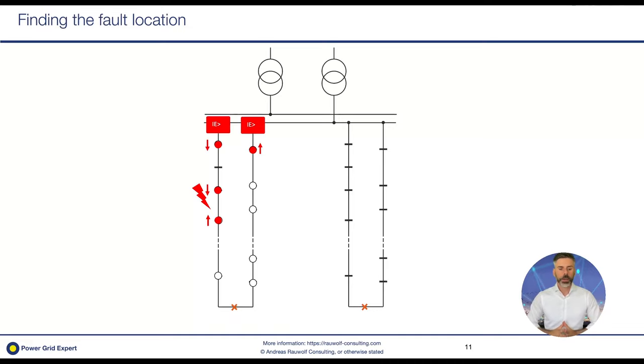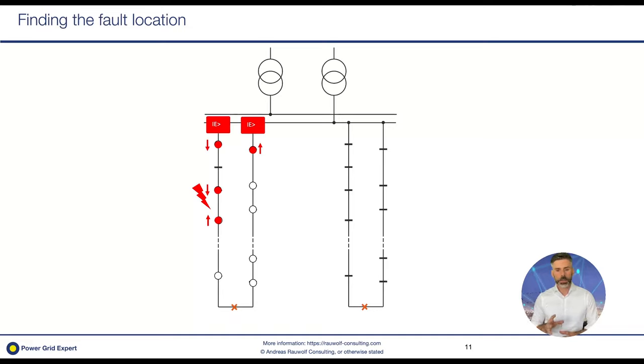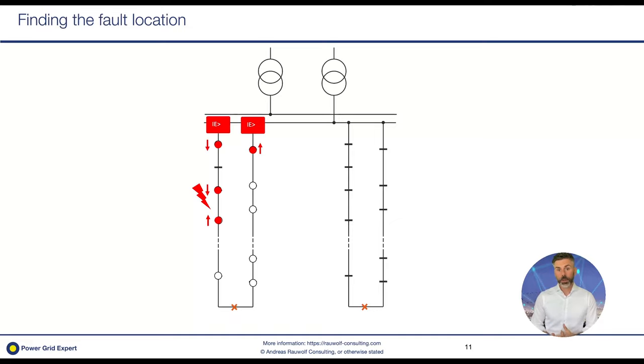Even with one indicator in the middle of a feeder, you can already narrow down the fault location, making the search much quicker. The more indicators you have, the better — once the full feeder is equipped, no switchover is needed at all. This is a big advantage because during an earth fault there is higher voltage on the healthy phases, increasing the risk that a weak point such as a cable joint or potential transformer fails, causing a double earth fault. Narrowing down the search time and clearing the fault as quickly as possible is therefore a huge advantage.